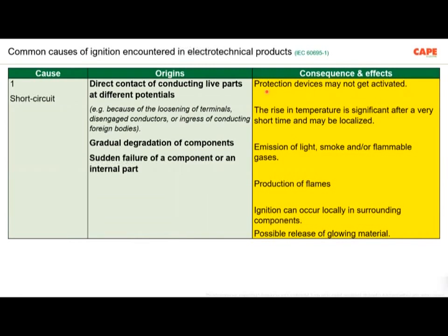One of the factors which is influencing this parameter is earthing. In case of an earth fault, if your earth fault return path is poor, of course your protective devices don't operate. As a result, you will get into trouble. Number 2, the rise in temperature is significant after a very short time and may be localized. That means a hotspot inside your equipment in a very small area. And if the temperature is sustained for a longer duration, of course, the short circuit happens.